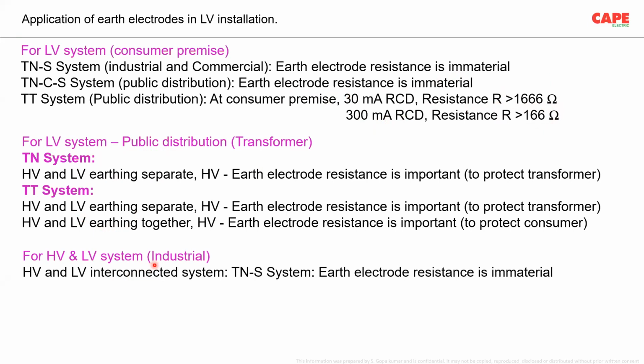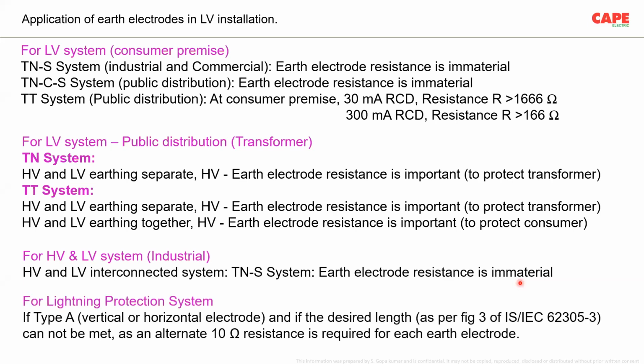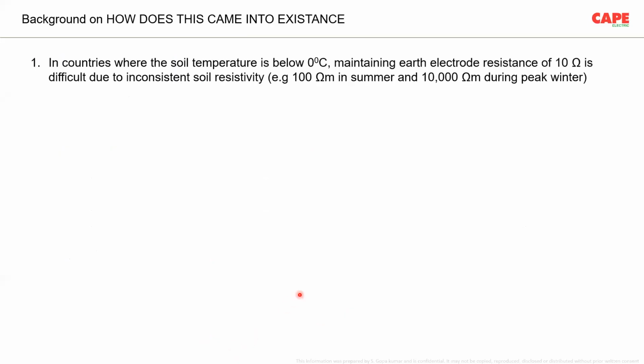And if you go for an industrial system, actually the earth electrode resistance is immaterial. If you have your own transformer or your own DG, and if these are within your control, very close to your premise, technically speaking, these are actually immaterial. The only place where you need a 10 ohm earth resistance is for lightning down conductor earthing, type A. Now, what is the background?